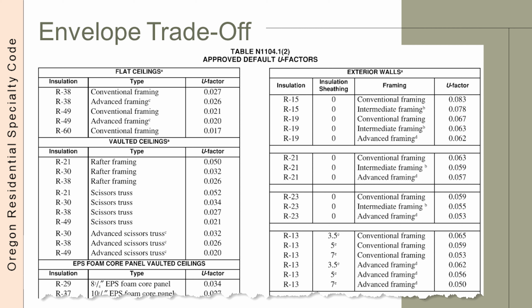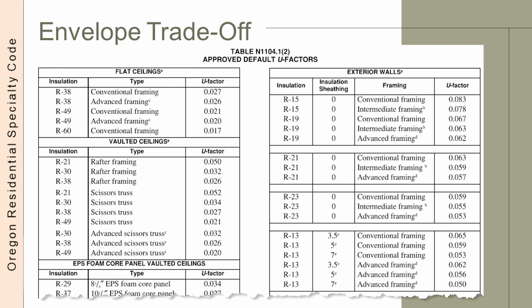Before moving on, there are some assemblies that aren't common in residential construction. In these circumstances, the designer or builder can go to Appendix A of ASHRAE Standard 90.1 to find more assemblies and methods to determine special assembly U factors. If not from Table N1104.1(2), you should get a full calculation document from the designer as part of the record drawings.